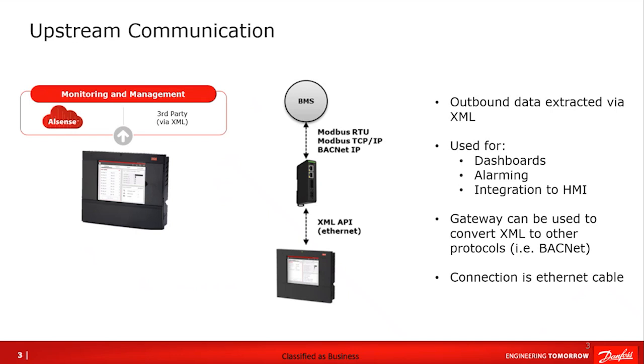The reasons that data is being extracted include dashboards — pulling in data to display history trending on case temperatures, rack pressures, and these types of things so the user can understand performance of their system. Alarming, if an alarm occurs on a system, to get notification out to the proper parties — whether a technician or contractor — so they could look into servicing the rack or system as needed. And for people looking to extract data to a higher-level device, that would also be an option through these XML commands.